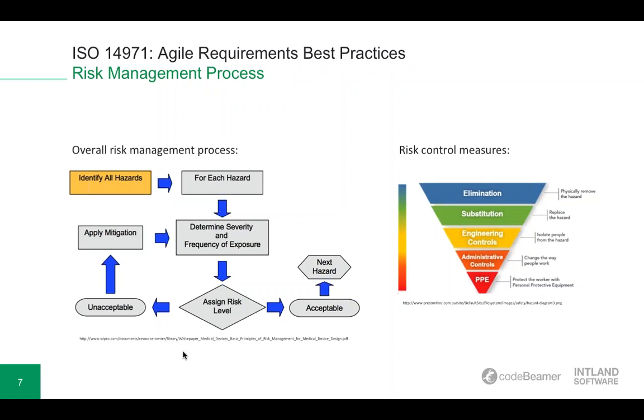Okay, but how should you approach this process? The most important aspect of risk management is anticipating the possible failures of the system. You have to define control measures, whether they are inherently safe, preventive, corrective, or informative. And each failure should lead to risk control measures, or RCMs, and each RCM should lead to requirements implemented in the product hardware, software, or the documentation. Now, here on the right-hand side, you can see the different types of risk control measures.